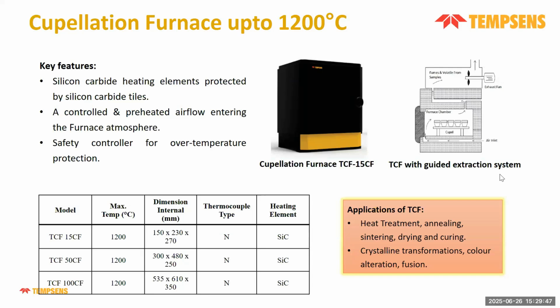Okay, and we have different models available with it. One is TCF 15 CF, TCF 50 CF, and TCF 100 CF. Each model can go up to 1200 degrees centigrade, and each furnace has a silicon carbide heating element with silicon carbide plates covering it, and the dimension is given there. So the dimension can be different. It depends on the number of cupels we want to put inside the cupellation furnace.